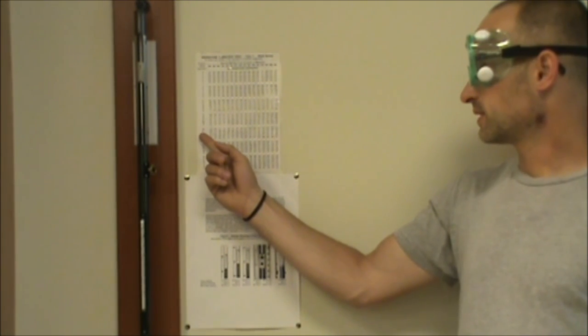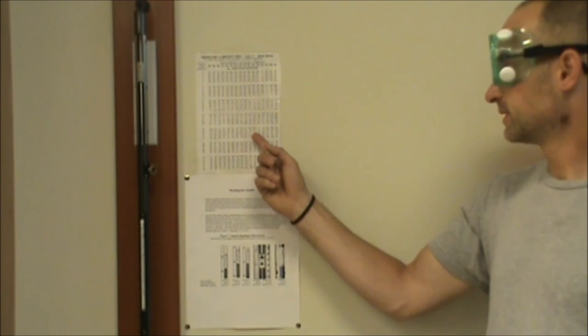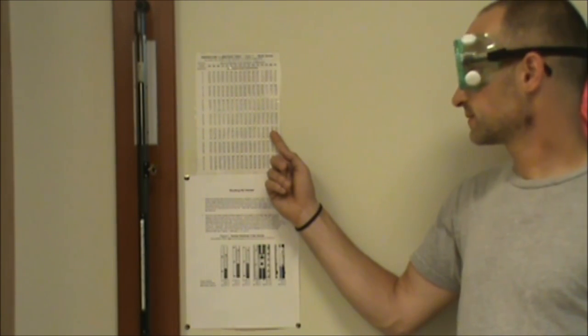We're then going to want to go across the row until we reach the value for 760 millimeters of mercury, because that's the value closest to the initial value we measured. And what we see here from our table is a value of 2.6. What that means is the initial measurement we took off the barometer is actually 2.6 millimeters too high due to the thermal expansion of that mercury.